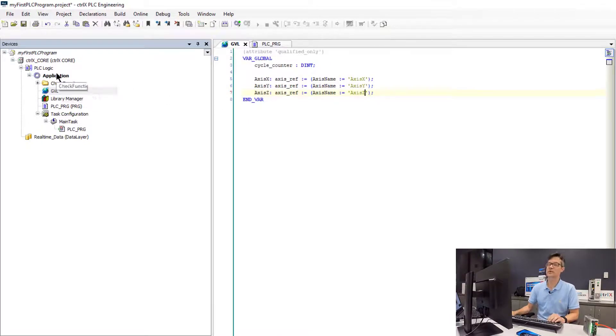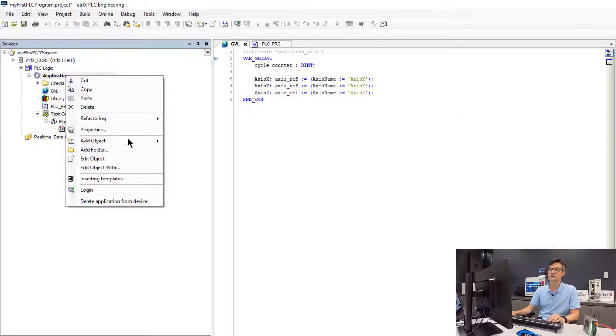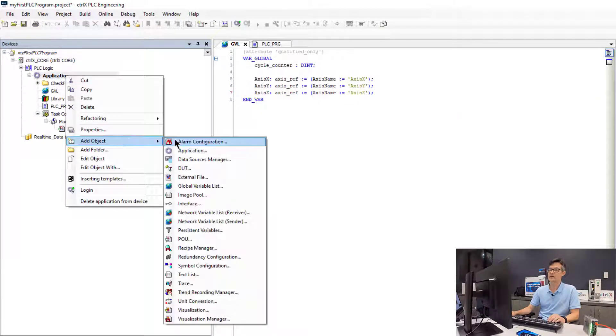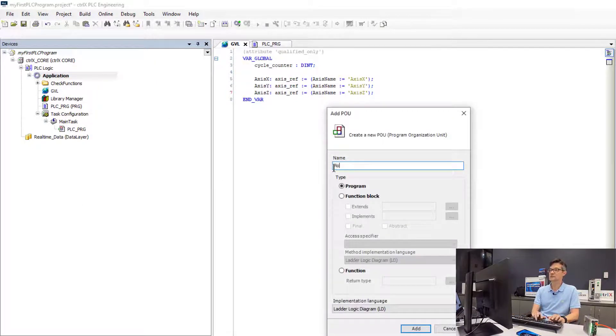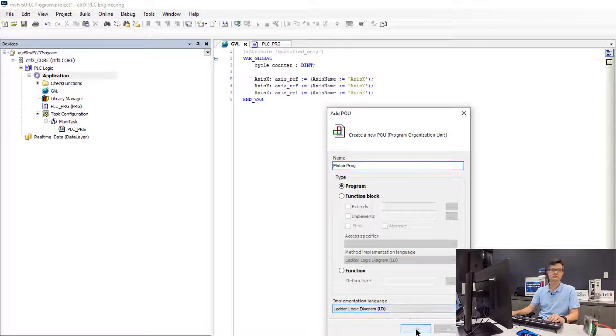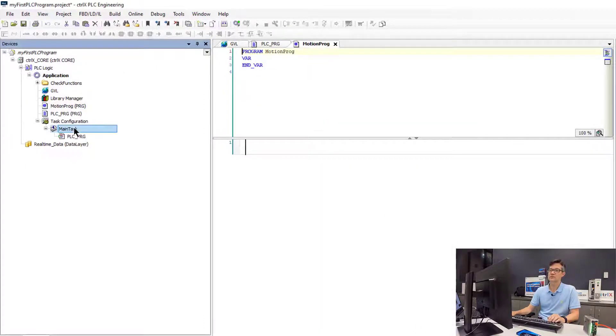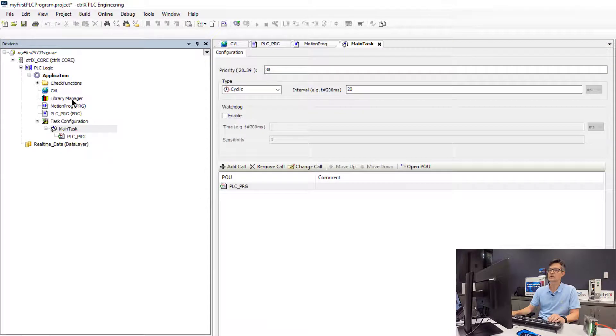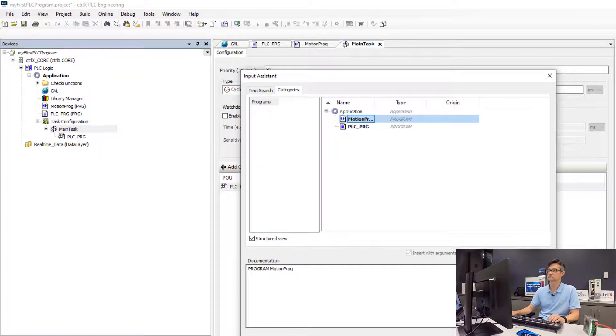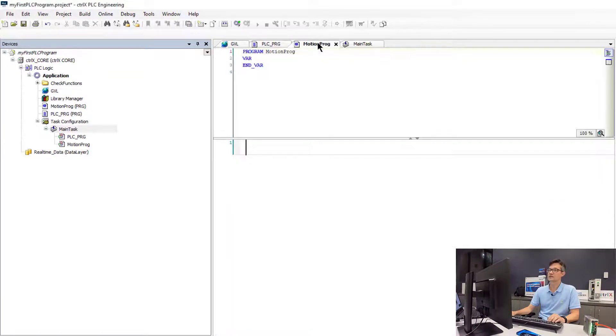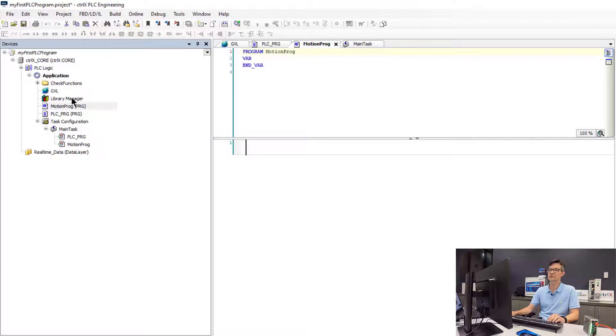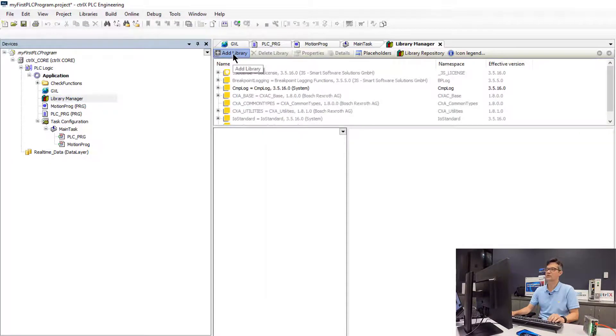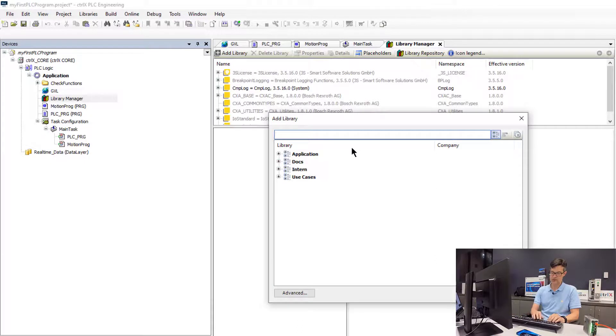So now we need to create a program which we will use to move our axes. So we will go back to the application area and we will add another object which will be a POU. In this case we will call it Motion Prog, and we will implement this one in ladder logic. The first thing we will do is we will schedule this program to be called in the main task. The next thing we need to do is we need to add the library that gives us the function blocks to control the motion using PLC Open function blocks. We will go ahead and we will add a library. A quick way is to search for PLC Open.